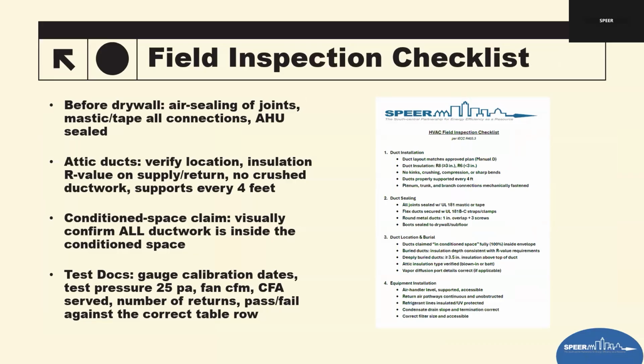Another quick field inspection checklist. I'm also going to include this with the survey email. Before drywall and rough-in stage, basically before ducts get buried behind drywall, inspectors should confirm that all joints, seams, and connections are sealed using UL 181 rated mastic or tapes. Check that the air handler cabinet is sealed as well, including the return plenum and any filter boxes. This is your best time, and sometimes only chance, to see all of the duct system in its entirety.